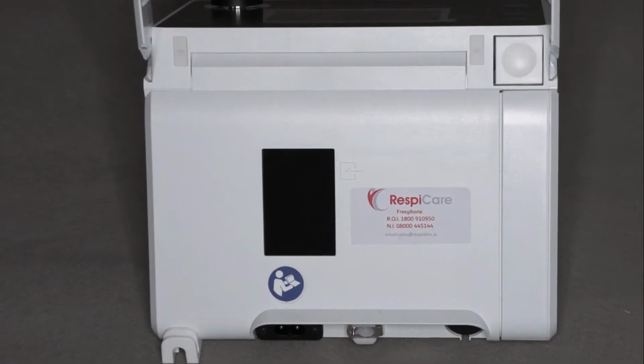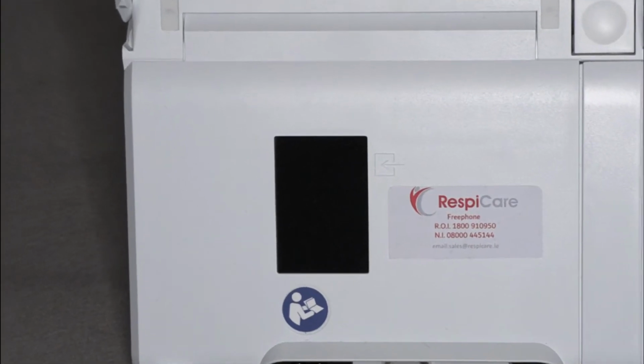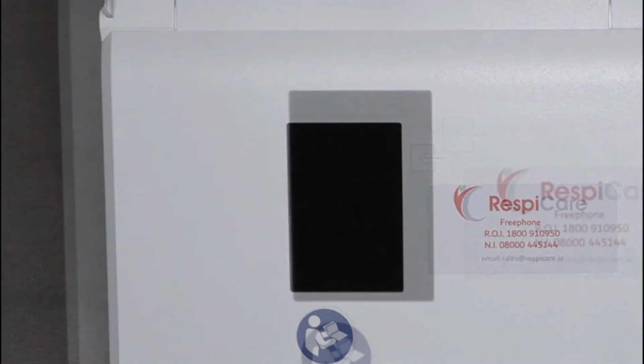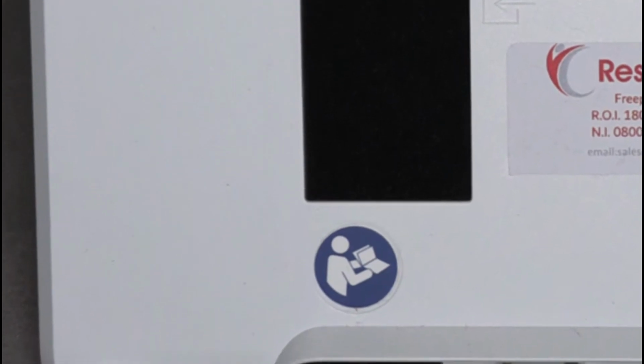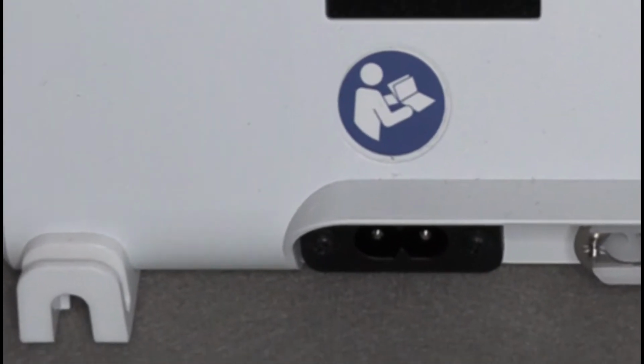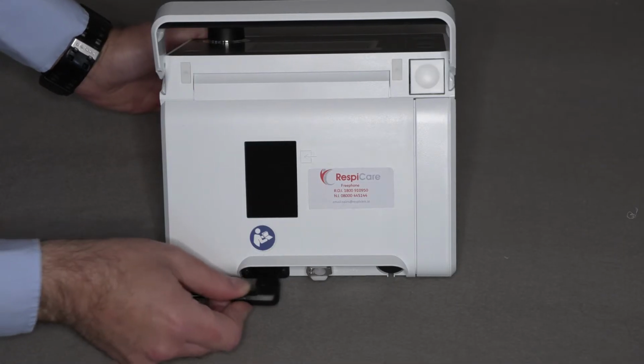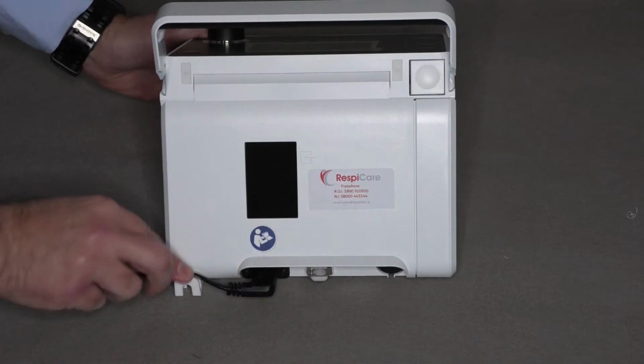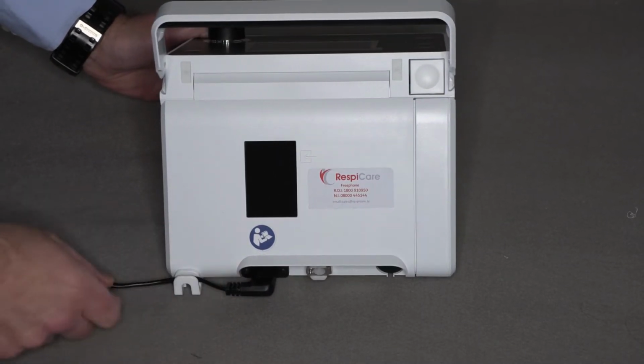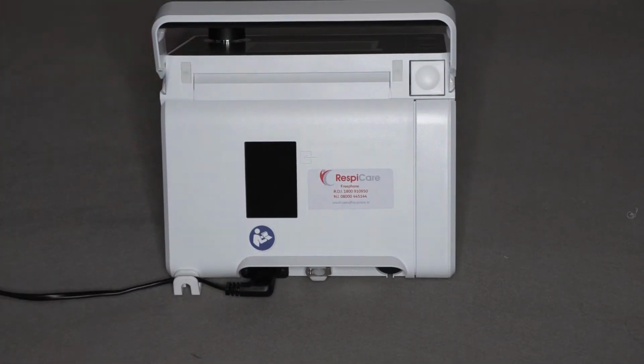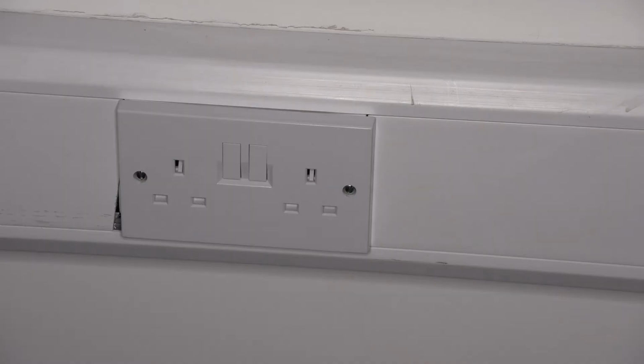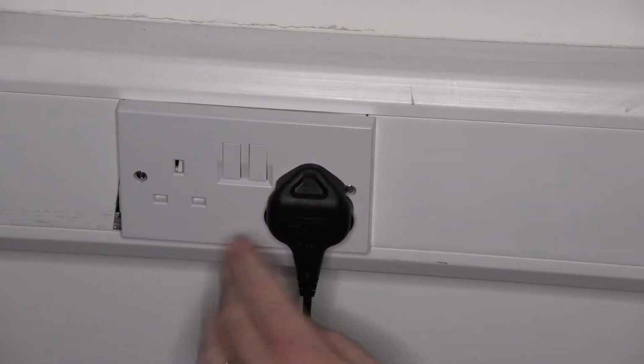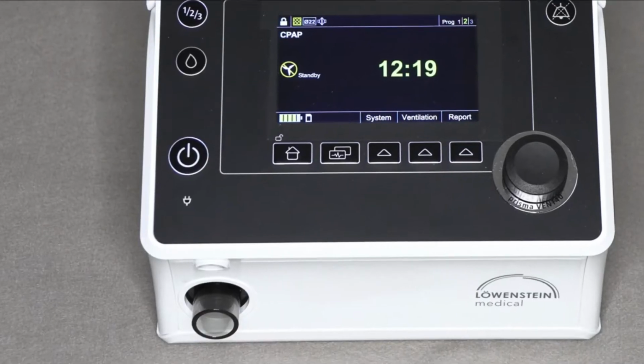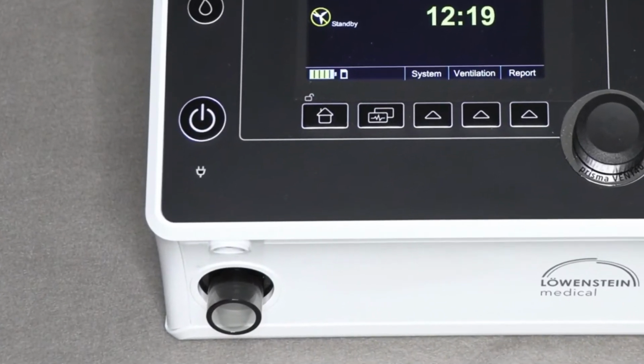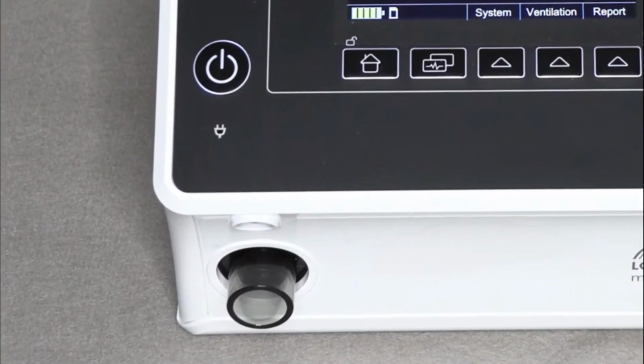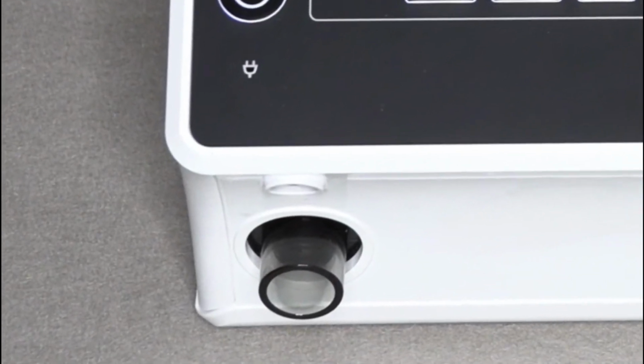At the rear of prismaVENT, you'll find filters where the air is drawn into the ventilator. You'll also find where the mains power cable can be connected. Once connected, the cable can be secured by using the mains cable support, which prevents accidental disconnection from power. The plug can be inserted into the mains socket on the wall. At the front of prismaVENT, you'll see the outlet port where the breathing tube will be attached.